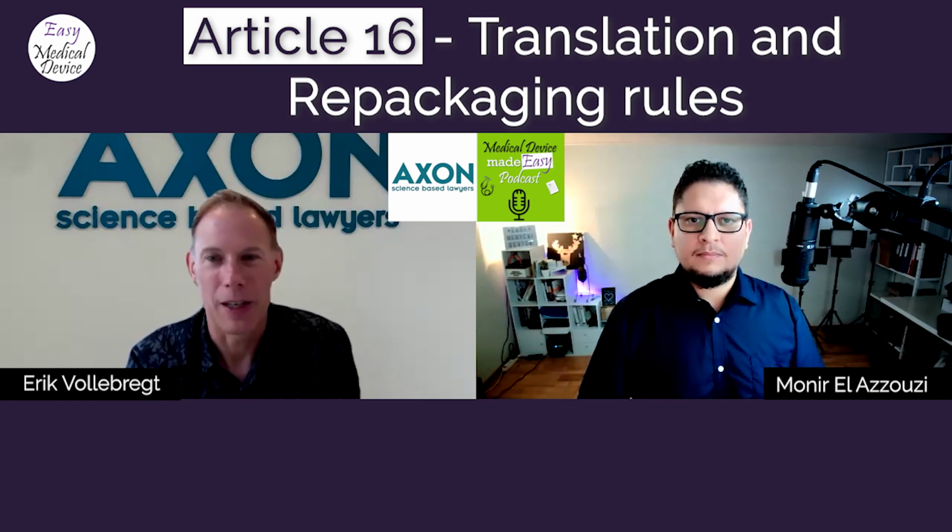specifically, because you can see that the EU has made the policy change to depart from the Sterling Drug case law, saying any device placed on the market that you don't basically adulterate in the process of repacking or translation, you can basically do whatever you like. They went to a situation where they said, well, we are going to align it to the pharmaceuticals parallel import and trademark case law. And then they also added on top the notified body quality management system certification, which does make this activity more complex.